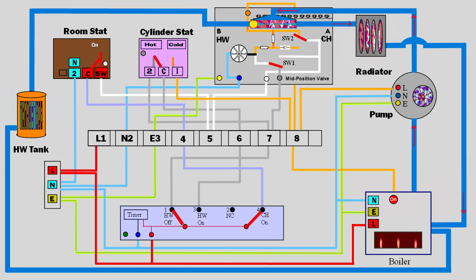When the room stat is turned off, the pump stops and the boiler turns off. But the mixing valve stalled motor is still being powered by the hot water off switch, and that is why it gets so hot. It is just a strange feature of this system.